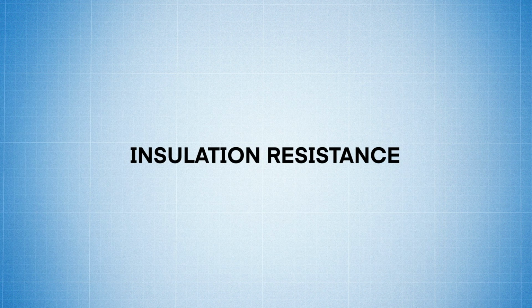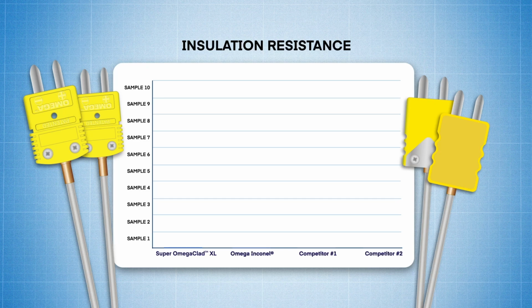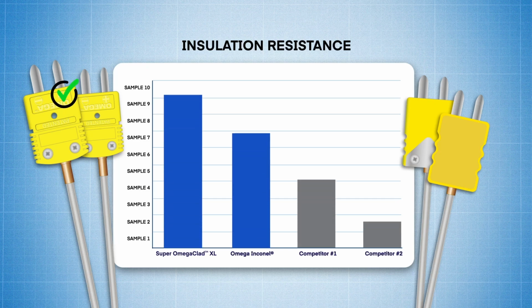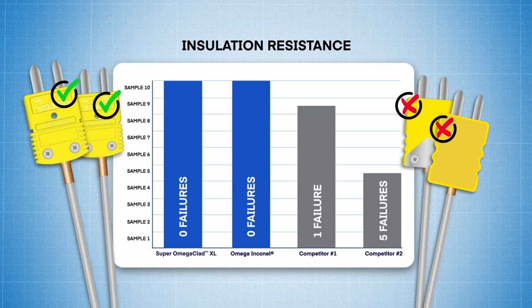And for the insulation resistance test, we checked the insulation resistance of each probe at ambient temperature with 500 volts DC, and our probes came out on top with 0 insulation failures.